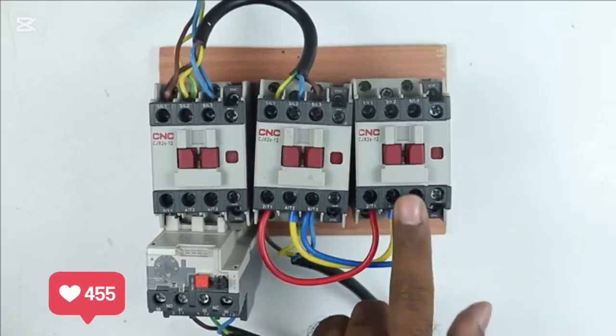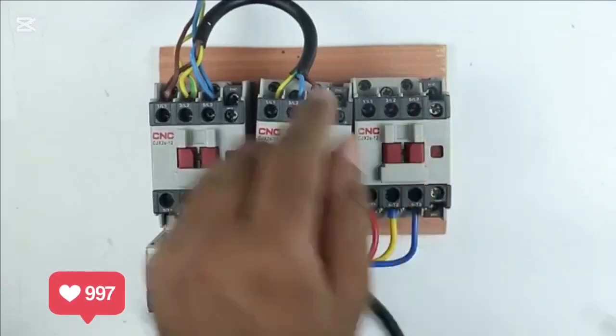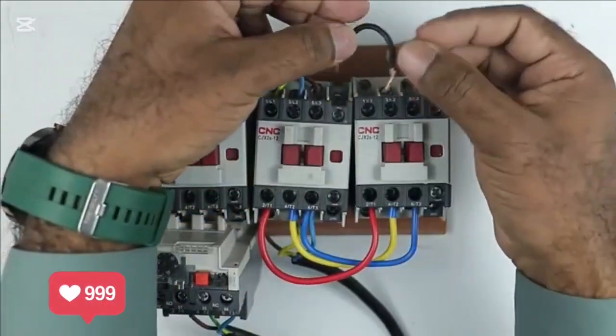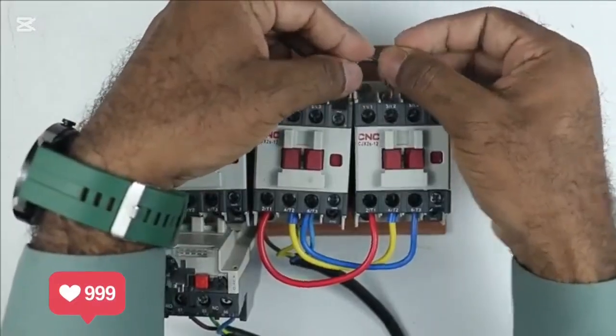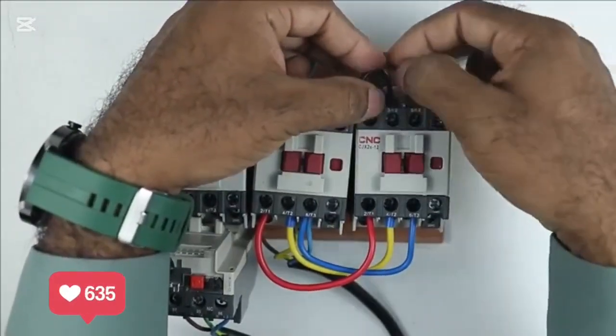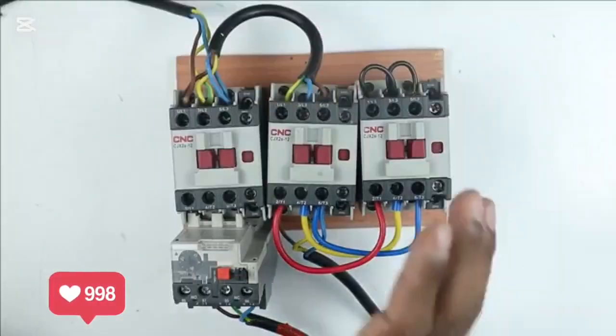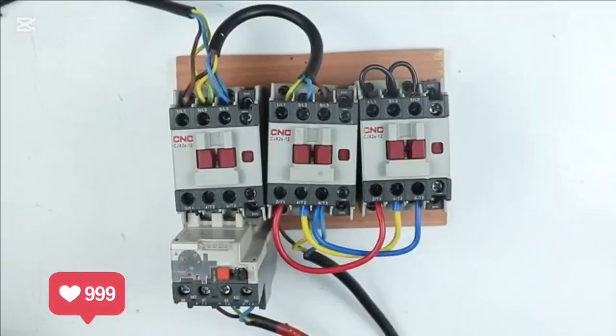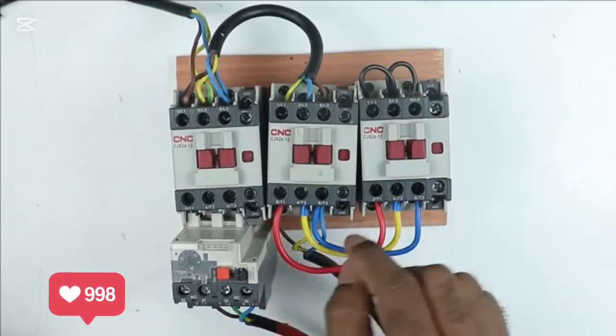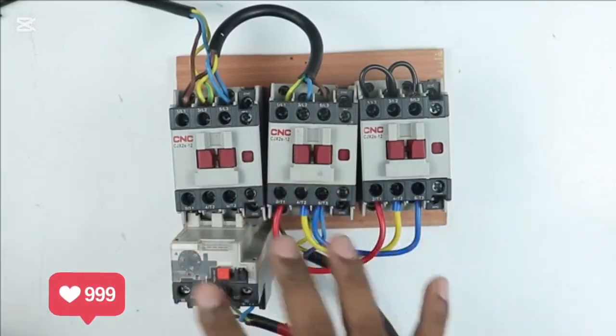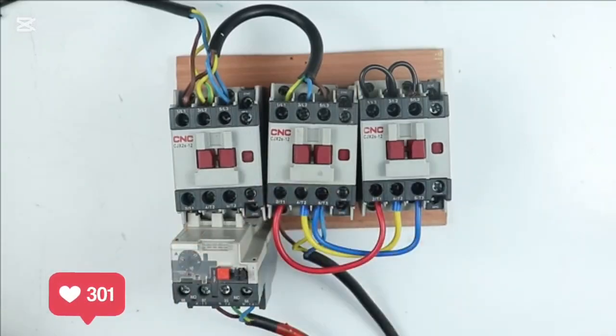Now in this star connection, the upper terminals here short these terminals. You can see I made a loop of 2 wires and connect this with all the 3 terminals. It means terminals are short with each other. So for this star delta starter, power wiring is completed. Before providing power supply to this, we must check the wiring again, because if you have done any mistake by chance, then short circuit may happen. So check at least once before starting.